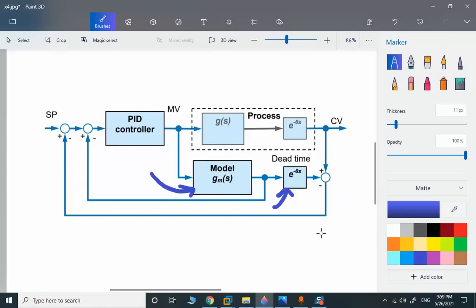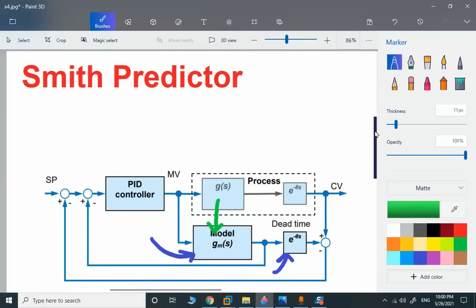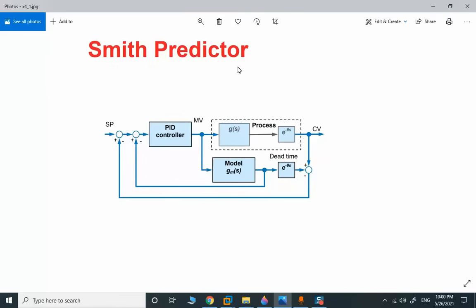You need to use offline tuning tools. I will provide the link for one of those offline tuning tools available for Android devices. When we find out the time constant and gain for the main model and the dead time for the dead time section, we can implement this structure in the software. Gm represents the main process model without delay, and this section is related to the dead time only. This part in this section is in the field and the rest of the calculation is in the programming platform in the DCS.